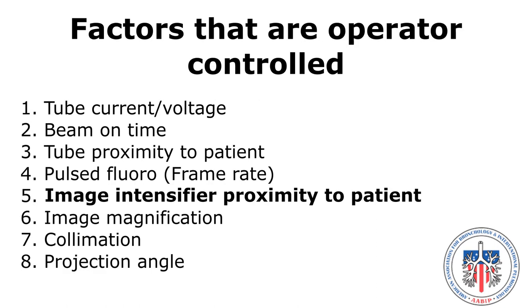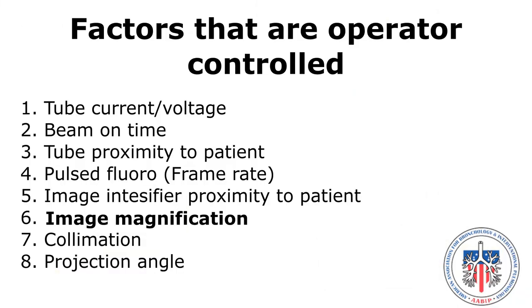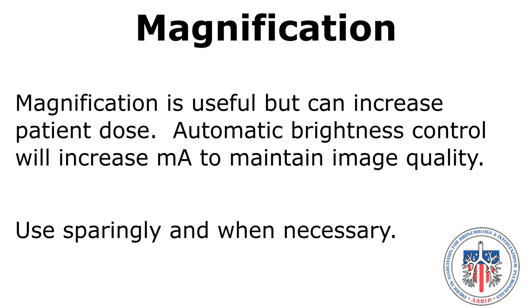Image intensifier proximity to the patient: the further away the image intensifier is from the patient, the more radiation noise and scatter occurs compared to when it is closer to the patient. Image magnification is useful but can increase patient dose. Automatic brightness control will increase milliamps to maintain image quality, so use magnification sparingly and only when necessary.